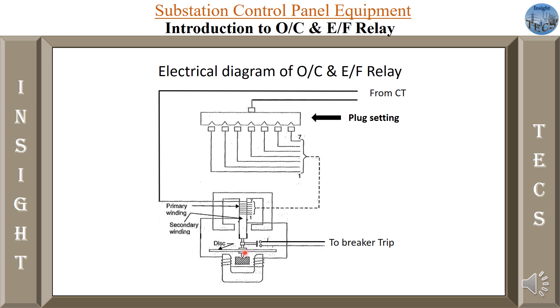According to Faraday's law of electromagnetic induction, torque is directly proportional to flux — more torque requires more flux. There is also a permanent magnet arrangement used to provide damping torque, which controls the speed of the disc. There are auxiliary contacts provided: as the disc rotates, these contacts convert from NO to NC. And there are plug settings, which are very useful to decide the speed of this disc — we will discuss these further in the video.